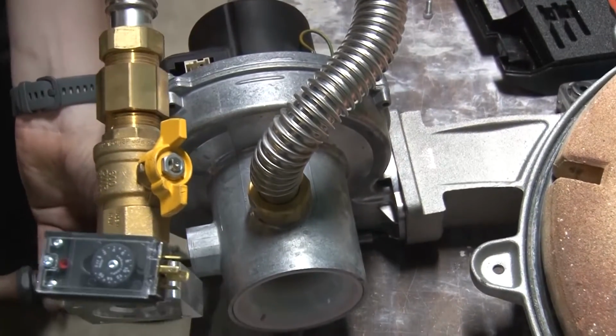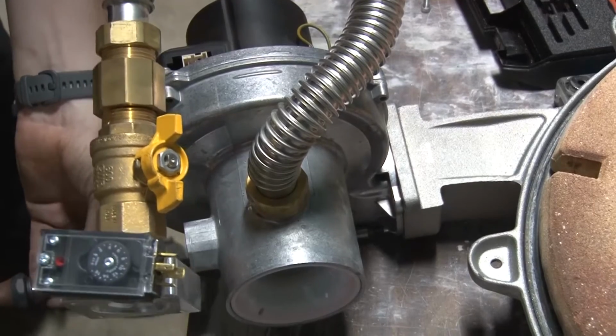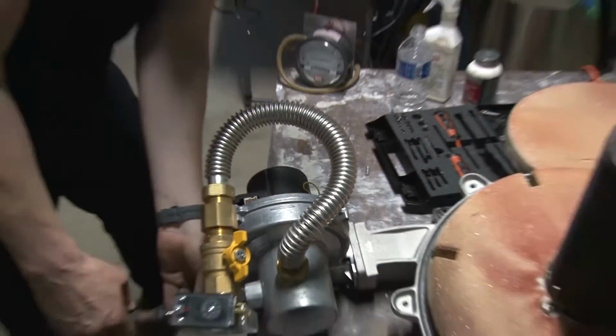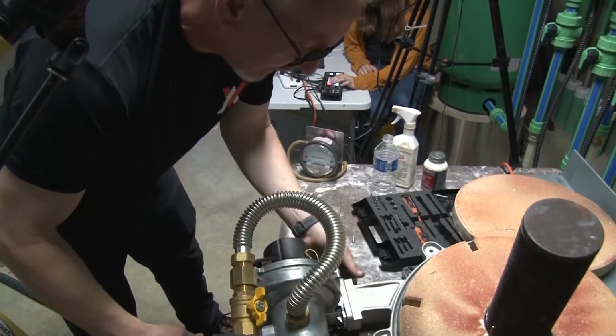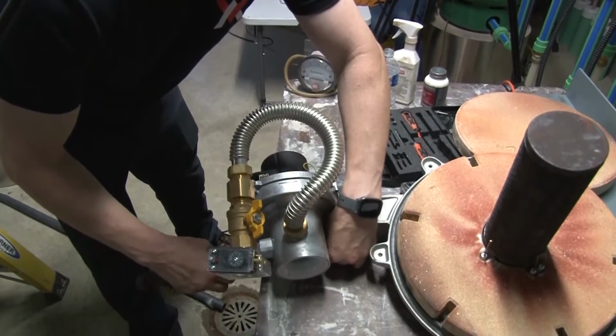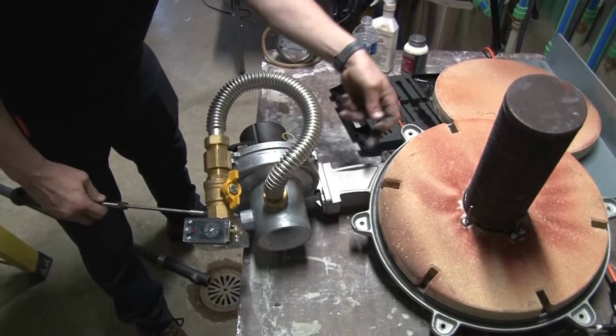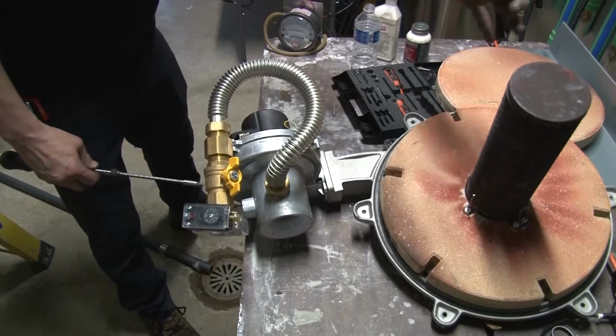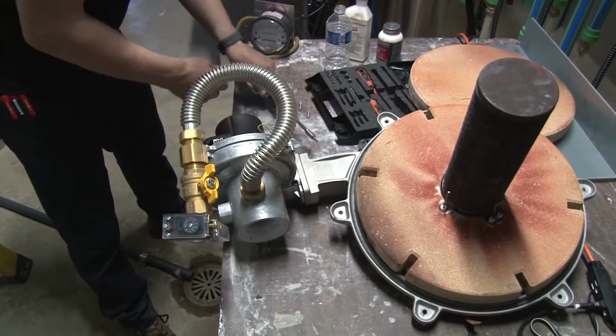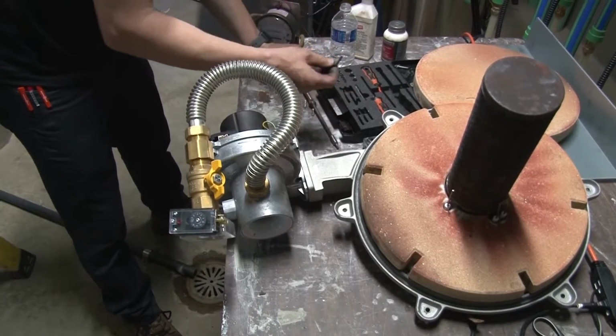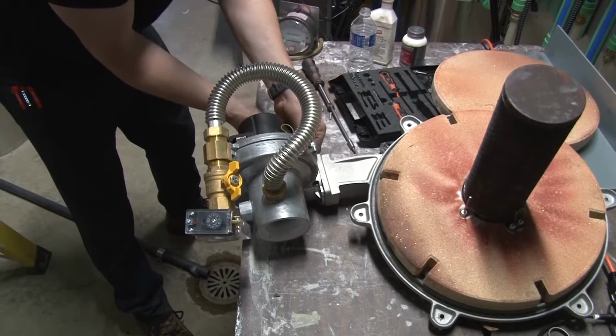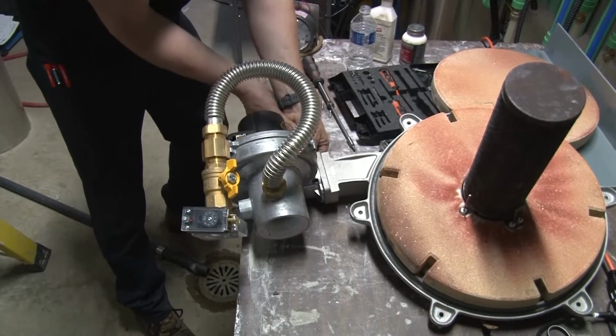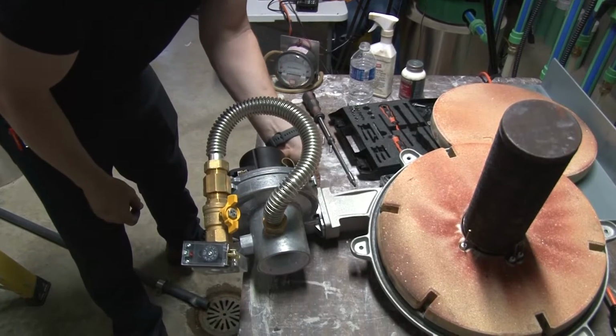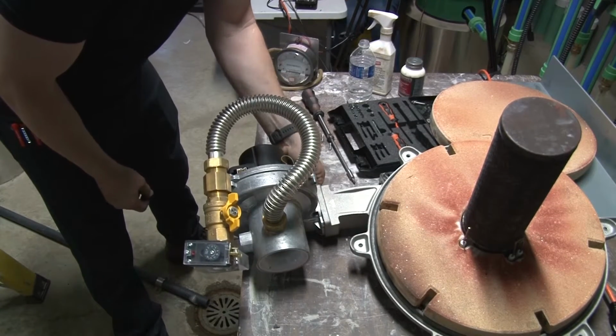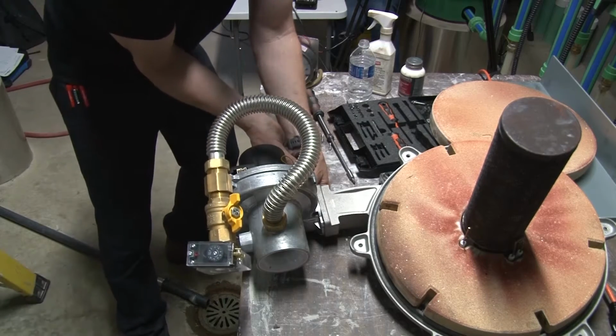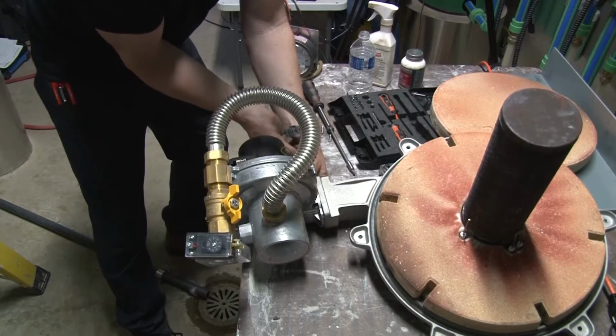and that burner stopped firing. If that flapper wasn't in there, your exhaust vent actually becomes a ventilation duct. And if it becomes a ventilation duct, the flue gas pulls through the vent, down through the burner again, through your burner tube, comes basically down the chamber here and comes out the venturi. And it damages components as it goes, that damp air. And that's going to cause your burner and your boiler to start breaking down. You're going to start getting some faults related to that. You'll start having more frequent service requirements for your boilers. You'll also have issues with parts. You have to have basically more repair parts for your burners and stuff like that. So it's important that we basically have a look at this.